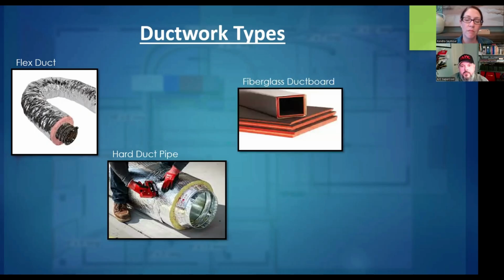Third is fiberglass duct board. This is somewhat rigid, dense, foil-faced, comes in sheets, and is typically fabricated on site. This is another entry-level, builder-grade type material that I don't use personally. I don't like it—it's very flimsy, has a short life expectancy, and is very susceptible to damage. Clients tend to pile stuff on top of it and it collapses, and once it starts to degrade, it releases fibers into the air.